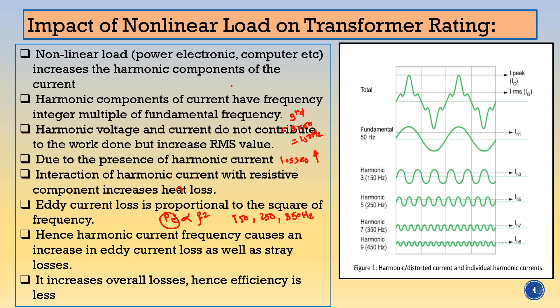Here you can see the nature of the harmonic current. If we extract the component of it, this is the 50 Hz component. If we add the third harmonic at 150 Hz, fifth harmonic at 250 Hz, seventh harmonic at 350 Hz, and ninth harmonic at 450 Hz together, the waveform is distorted. If we calculate the true RMS value of this, you will get an RMS value larger than the fundamental current. This increased RMS value impacts the losses, and hence the efficiency of the transformer goes on decreasing.